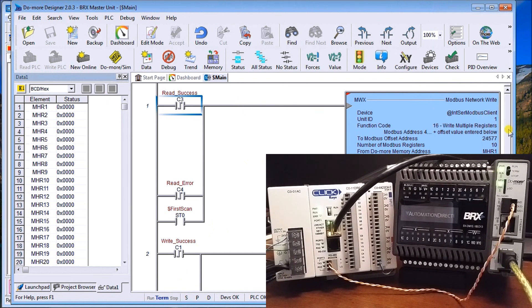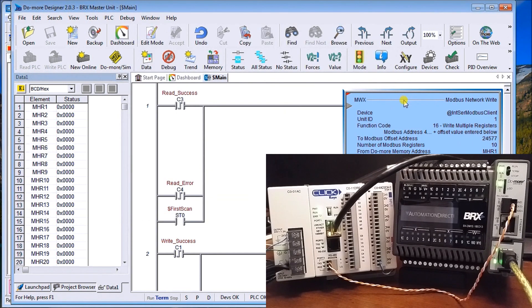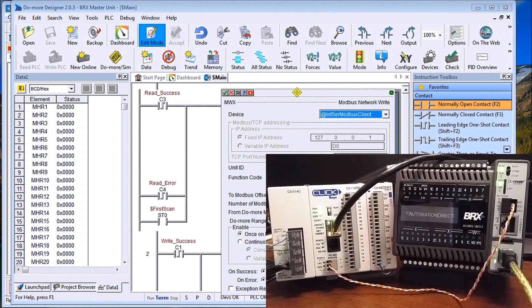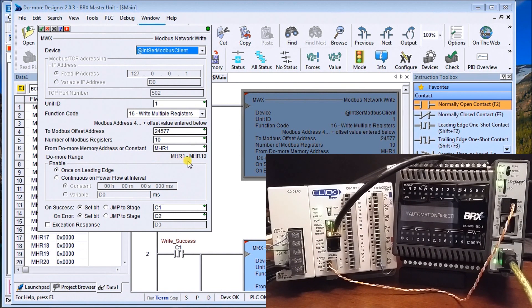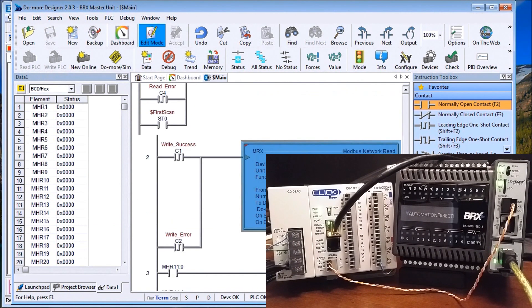Looking at the program, there are two instructions: a read instruction and a write instruction. Double-clicking the write instruction and going into edit mode, we can see: unit ID is set, we're writing multiple registers, the Modbus address is 4 plus an offset of 24577, the number of Modbus registers is 10, and from the DoMore address MHR1 — so the range is MHR1 to MHR10 — we're writing these out to the Click PLC.